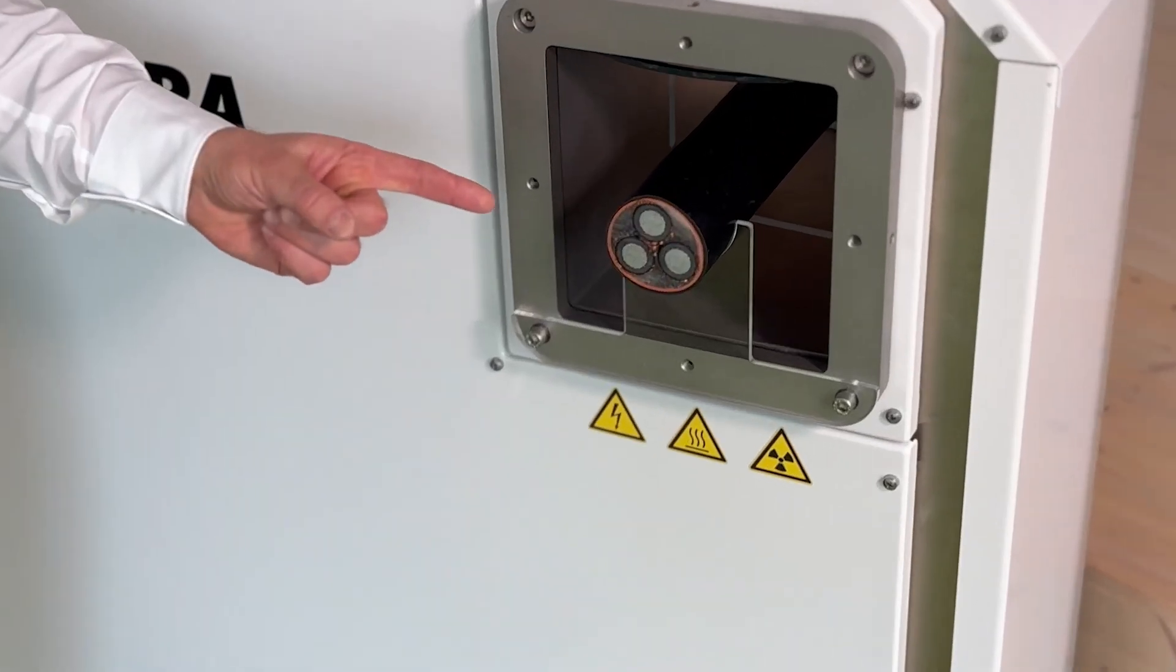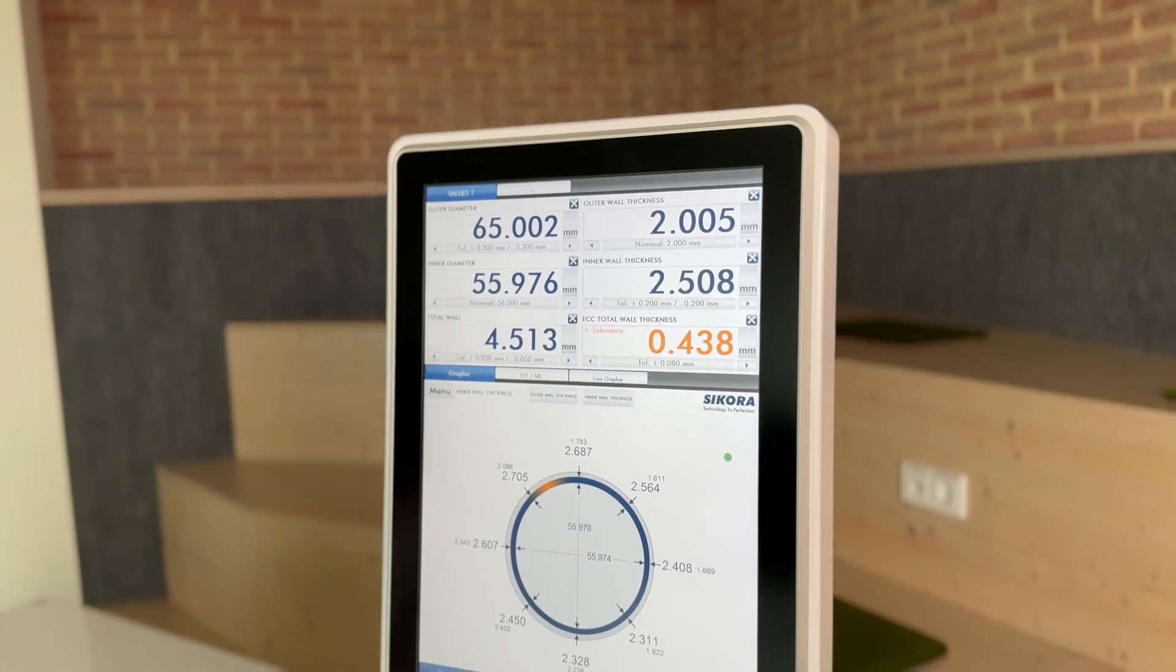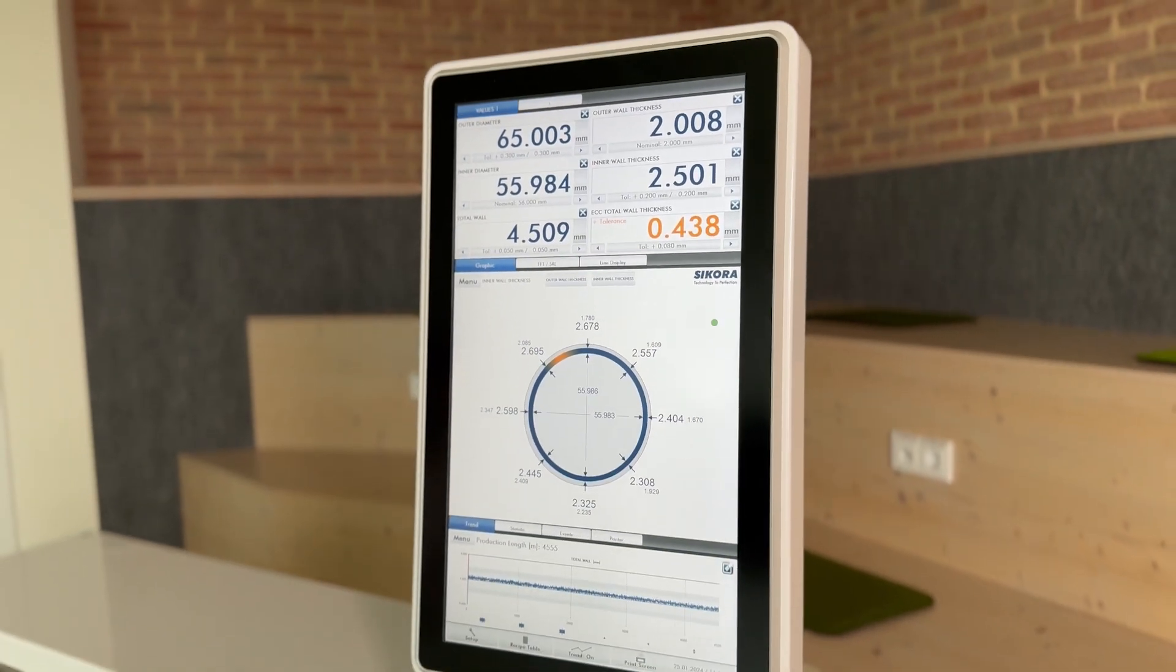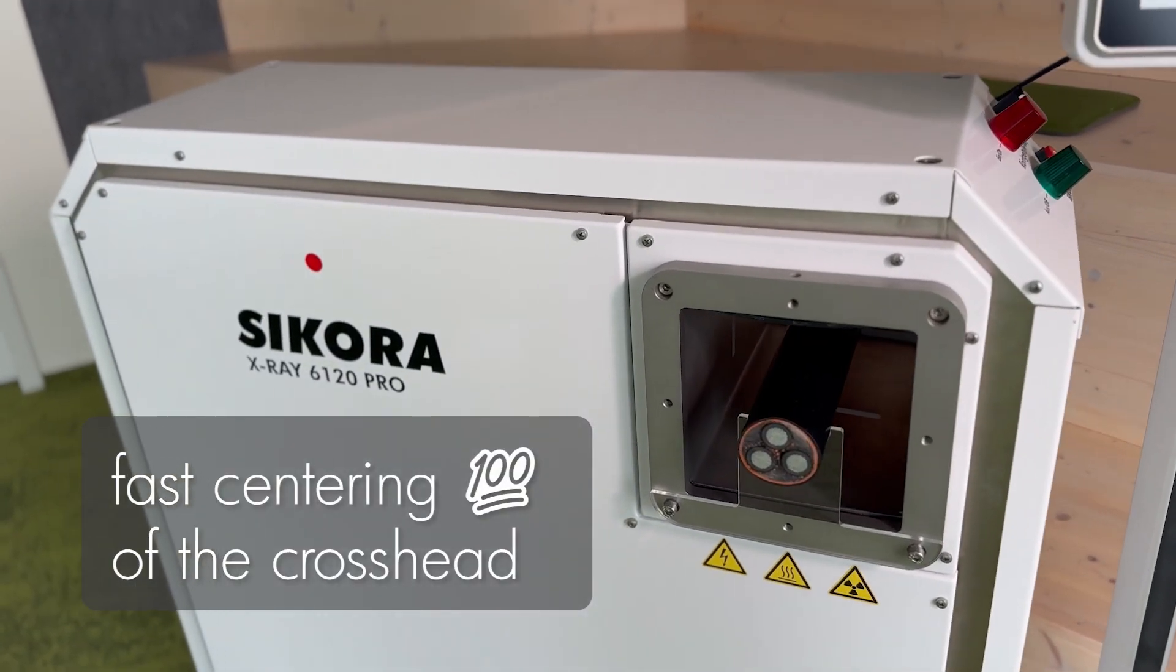It measures the wall thickness of insulation down to 0.1 mm, providing all the values and information the operator needs for fast centering of the extrusion process.